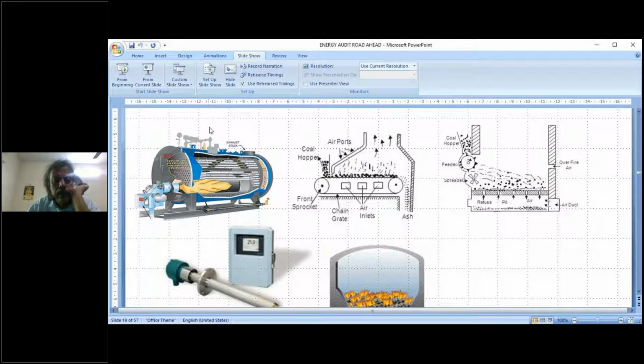So the target efficiency might be 83% or 84%, but measured efficiency is 80%. Where exactly are we losing? Is it because of using too much air, carried out as exhaust, or because of unburnt fuel? We need to do a detailed exercise on efficiency, finding where the 20% is going, why it's happening, and the reasons. Once you attack that, your efficiency can be improved. So this is the approach.